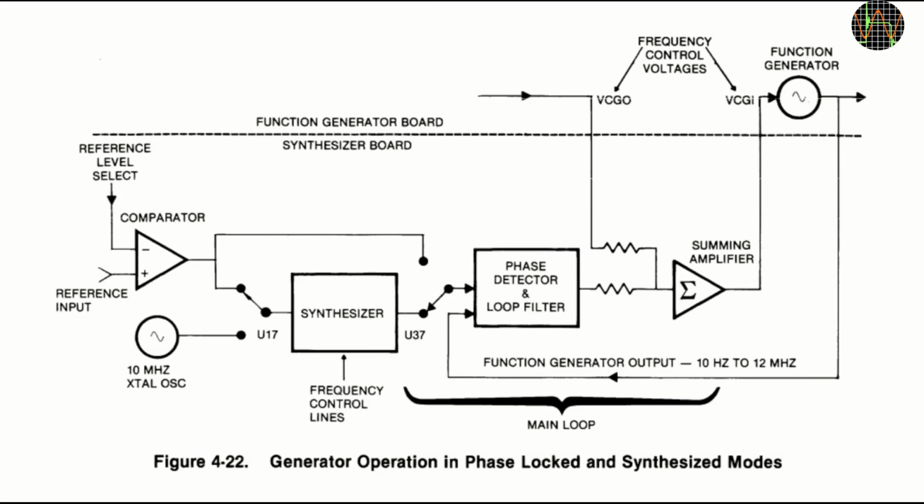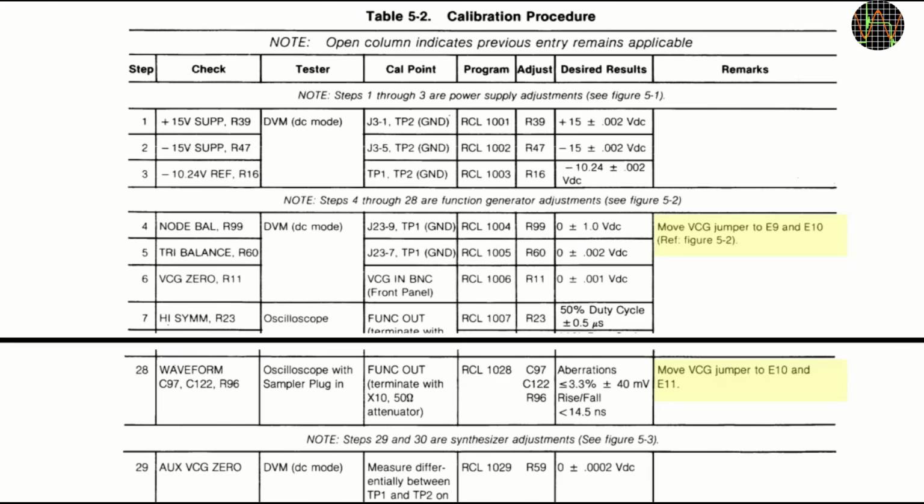The service manual is very comprehensive and just shy of 150 pages, not an easy read. While working my way through the functional description, I occasionally looked at other sections just for a change, so to say, one of which was calibration. I'm always interested to see how this is done and what inputs and equipment is needed. This part caught my eye, probably because it stands out in the otherwise empty remarks section and because of the problem with the PLL, which drives a voltage-controlled generator, VCG.